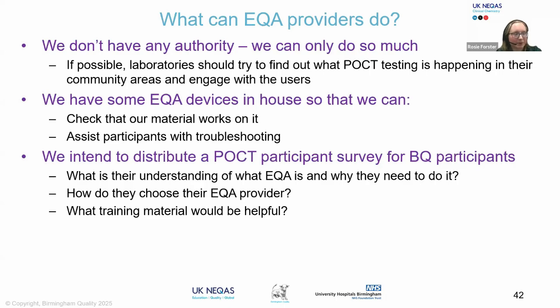We also have some of the EQA devices that our participants use in-house, and we often use these to check that our material is suitable for them, which it is because it is human whole blood, and to assist participants with their troubleshooting. This has been really useful because it's allowed us to replicate some of the problems that participants have seen. As an example, for one of the devices that we have in-house, we received a lot of messages at result submission about a particular error code. What we were able to find out was that the participants were actually running the EQA samples as though they were IQC material, in a QC mode, which was causing errors on the device. So we were then able to reach out to the participants and provide them with further training material to try and stop this from happening.